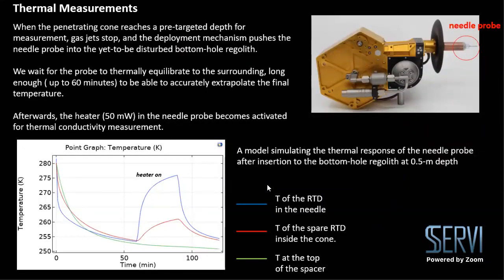In order to make the necessary measurements, at every half meter depth, when the needle sensor reaches the targeted depth, we stop blowing the gas. Then we push the needle into the soil at the bottom of the hole that is yet to be disturbed. First we spend an hour or so for the needle to thermally equilibrate with the surrounding soil. Especially in the first measurement at the half meter depth, the instrument will probably be considerably warmer than the surrounding regolith because we deploy the probe during the day.